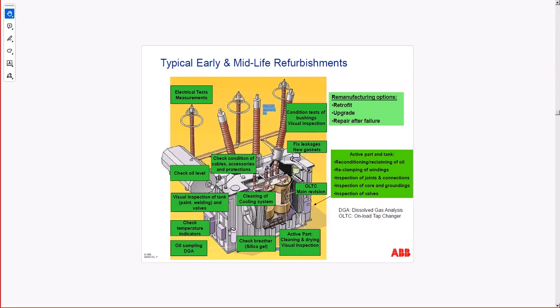Against overpressure of the oil, we have Buchholz relays. Buchholz relays actually measure the overpressure of the oil in the tank, and they act to disconnect the power if it goes up rapidly. Overpressure means an indication of possible explosion. Those overpressure relays act faster than differential relays. If an explosion happens in the transformer, the differential relay will actually be second in line after relay 63, the Buchholz, which is the fastest, as I said.